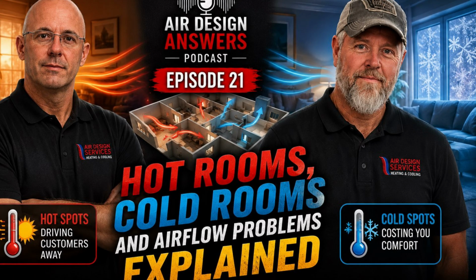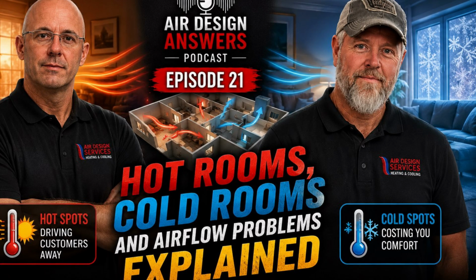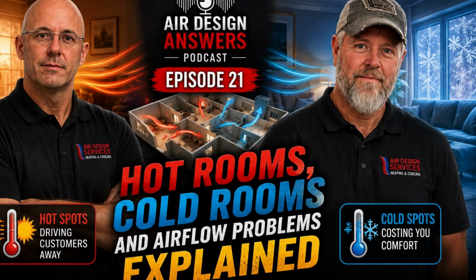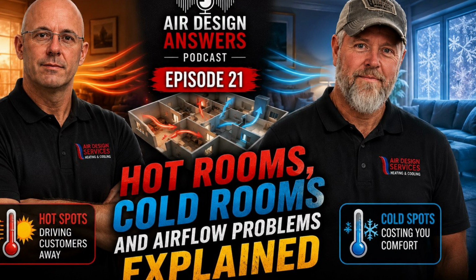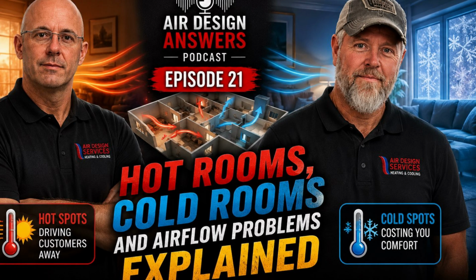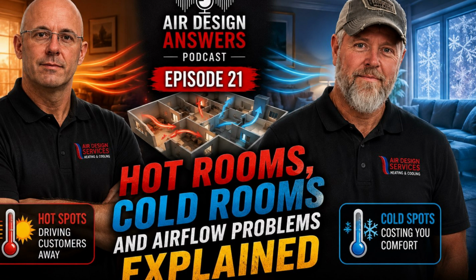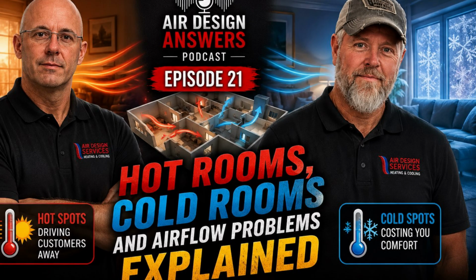One thing people rarely consider is how much technology has improved. Modern systems often include options like variable speed equipment, zoning systems, and advanced controls that weren't common years ago. And those technologies can help address comfort imbalances when they're applied correctly. But even then, technology isn't magic. You still need good ductwork. You still need proper airflow. You still need reasonable insulation and home performance.